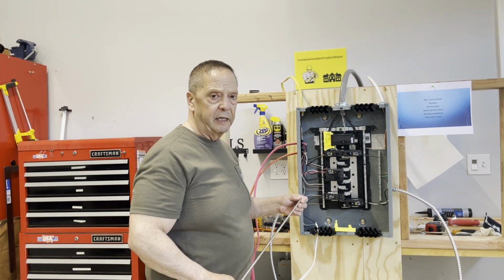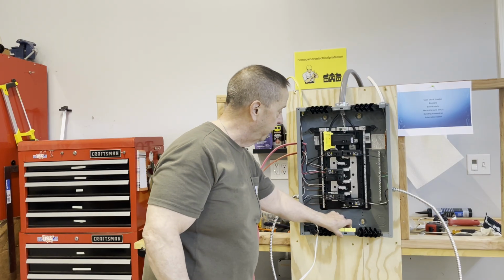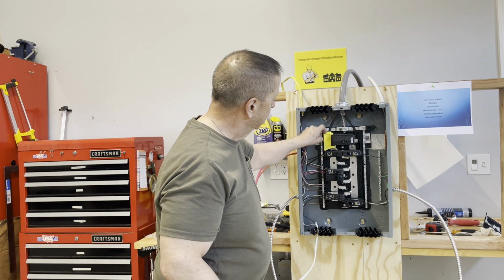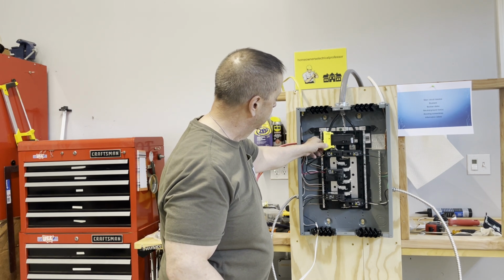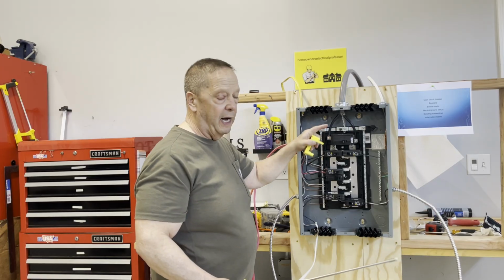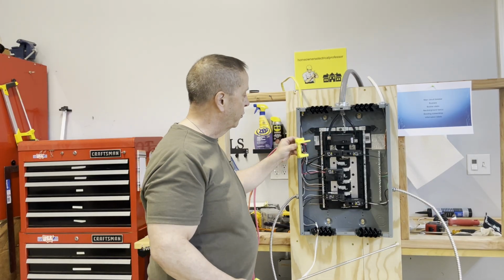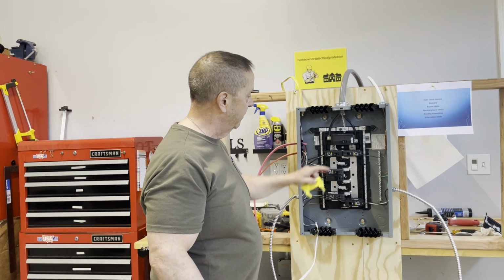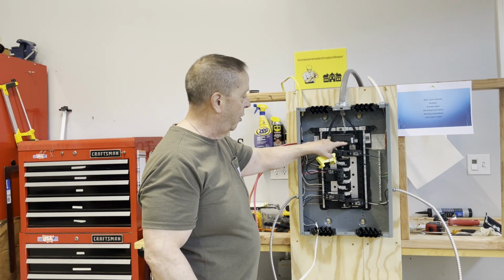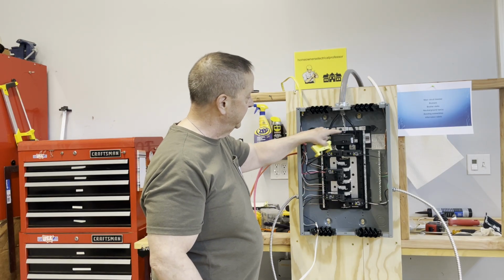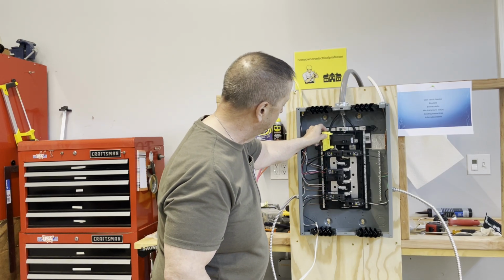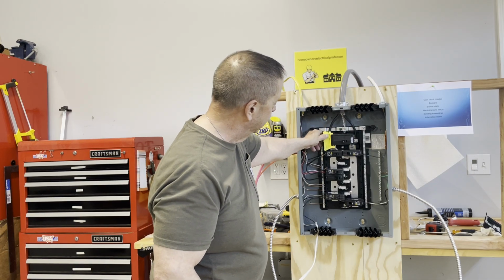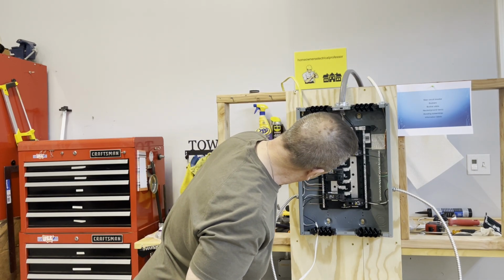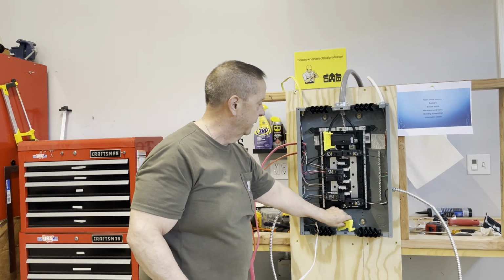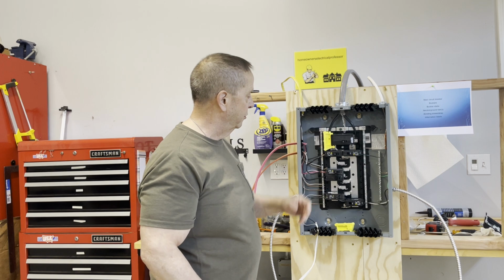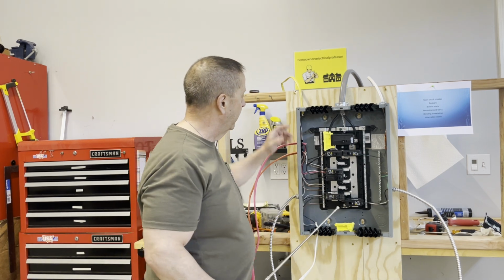Now, probably about 10 years ago, the code book started requiring that these two terminals here on the main breaker, they are always hot as long as the meter is in. So what they require now is even if you take the cover off and you turn the main breaker off, the bus bars are dead, but these two terminals are still hot. So what they require is when the panel is installed, that these covers are put on so that when you open up the panel, those two terminals are still covered. You can't touch them.